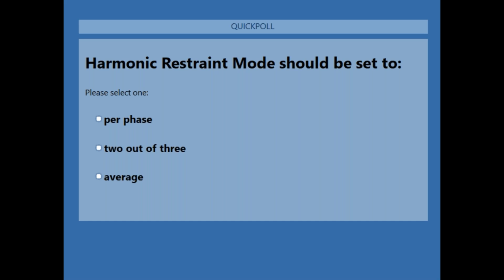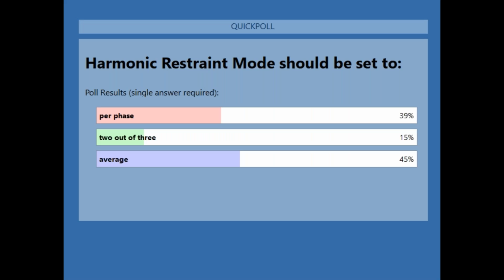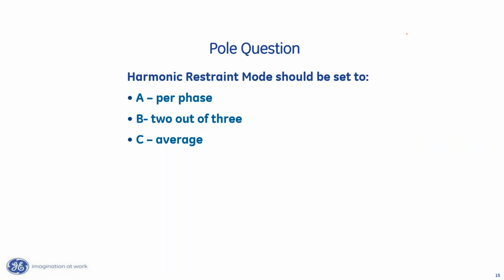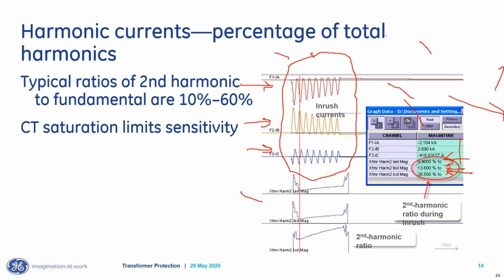And so let's go ahead and close the poll, and I'll talk about what I think the correct answer is. So, 45. Okay, so 39 said per phase. Yep. So let's go back and look at this data. If I did per phase, I energize this transformer, I'm not restraining on A and B phase. I'm restraining on C phase. I'd trip, right? So per phase for this transformer wouldn't be the correct answer.